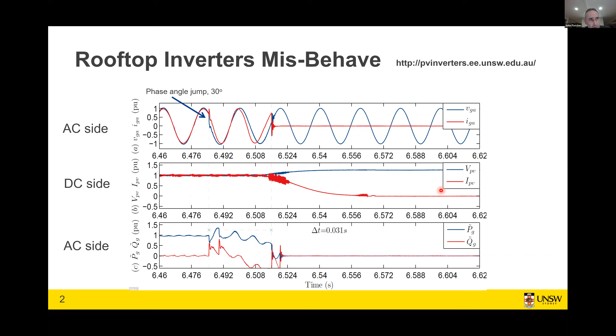Up until the time we started this work, there was no real understanding of how distributed PV could impact the wider network. The narrative here is that this really scared AEMO. We calculated that about 30% of the inverters connected to the grid, connecting rooftop PV systems, were vulnerable to relatively benign grid disturbances. That represented a 3 gigawatt contingency for AEMO, something they just hadn't been considering before. It just goes to show how you can really get yourself in a sticky situation very quickly with the great advances of distributed resources.